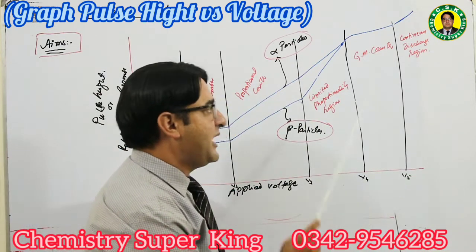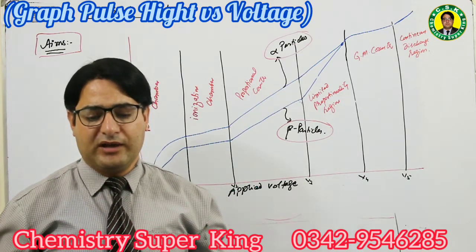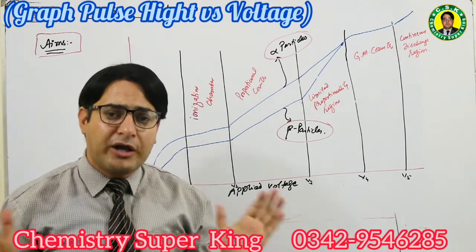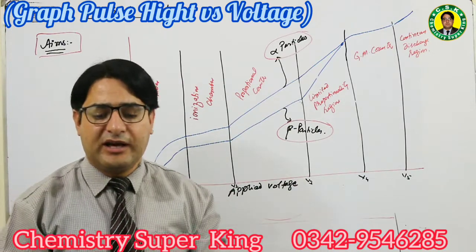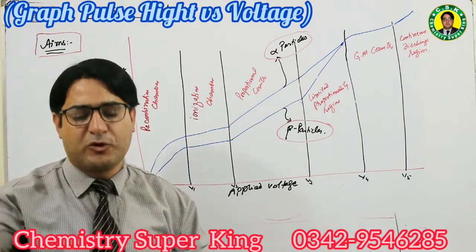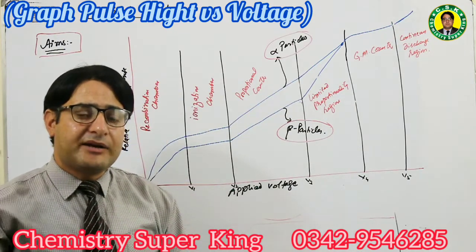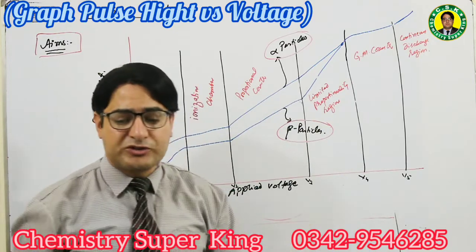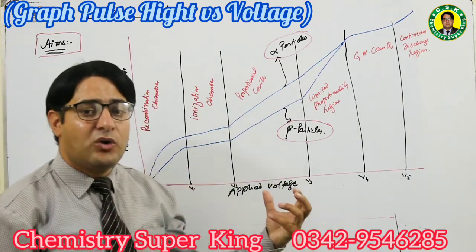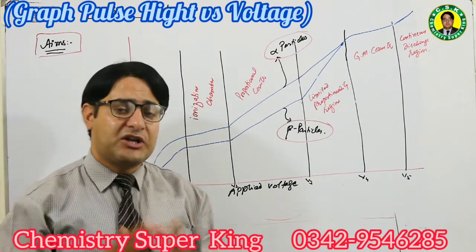Beyond V5, when voltage increases further, the filler gas starts to ionize by itself even without any nuclear particle entering the detector. The gas spontaneously ionizes and produces a continuous discharge, making the detector non-functional for detection purposes. Pulse height is no longer related to nuclear particle energy.